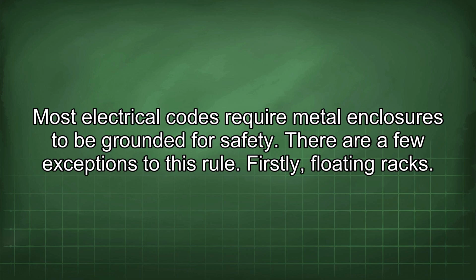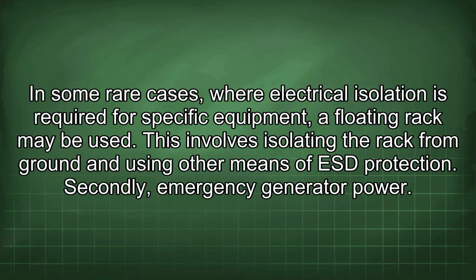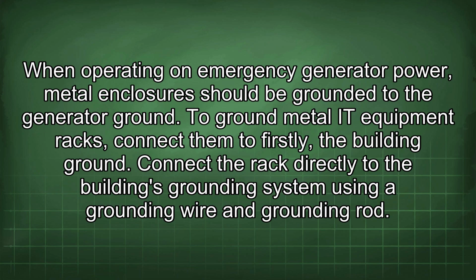Firstly, floating racks. In some rare cases, where electrical isolation is required for specific equipment, a floating rack may be used. This involves isolating the rack from ground and using other means of ESD protection. Secondly, emergency generator power. When operating on emergency generator power, metal enclosures should be grounded to the generator ground.